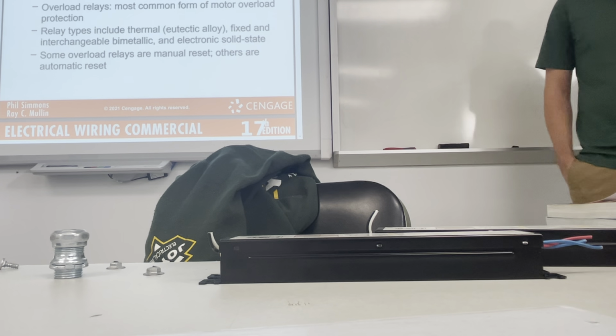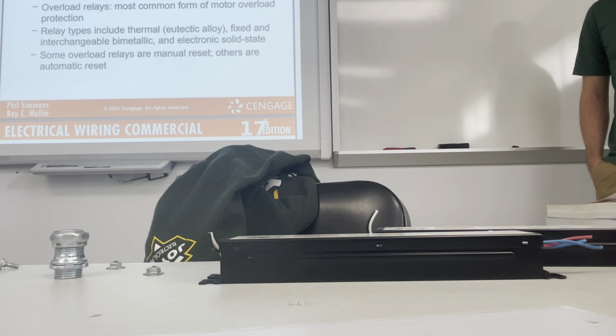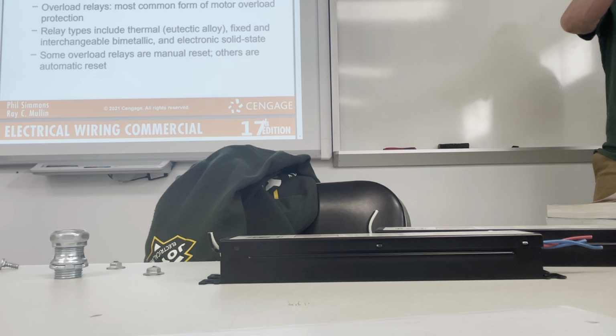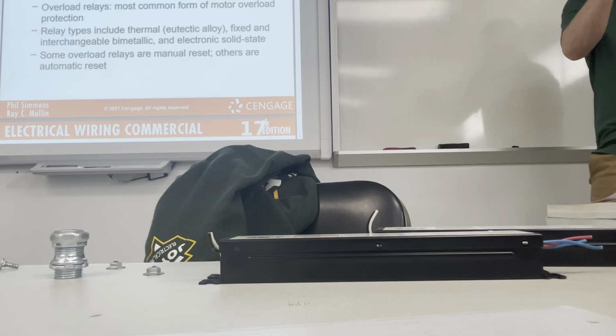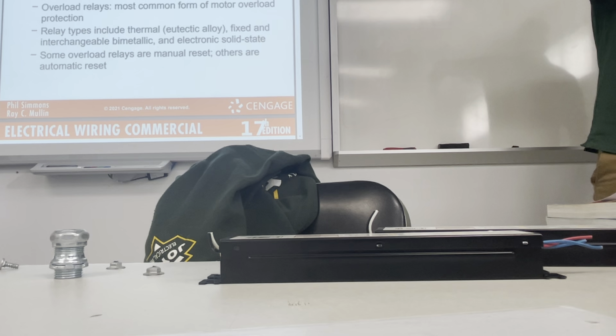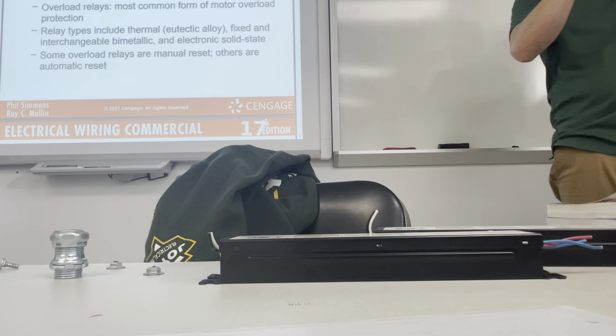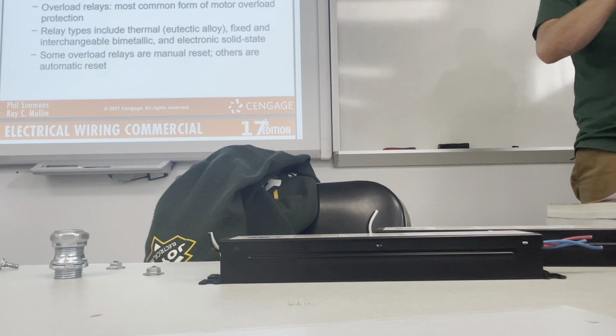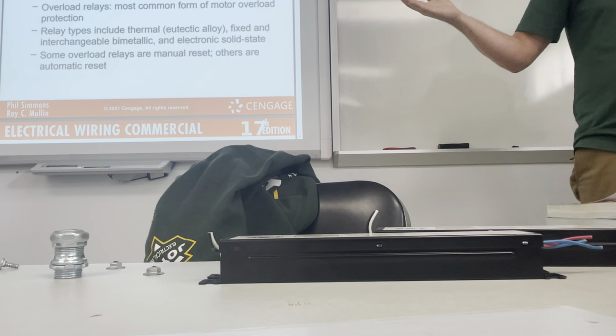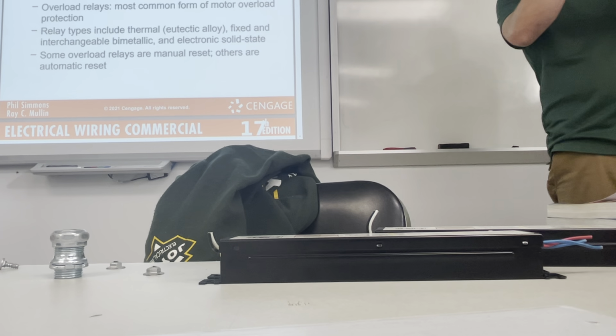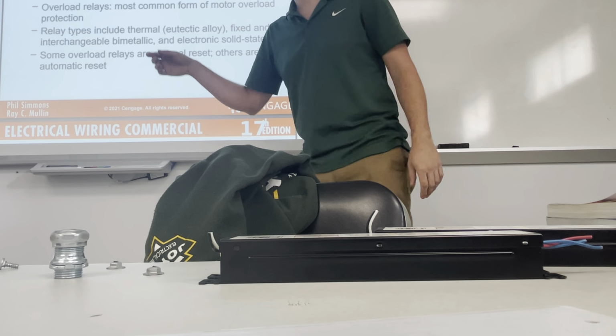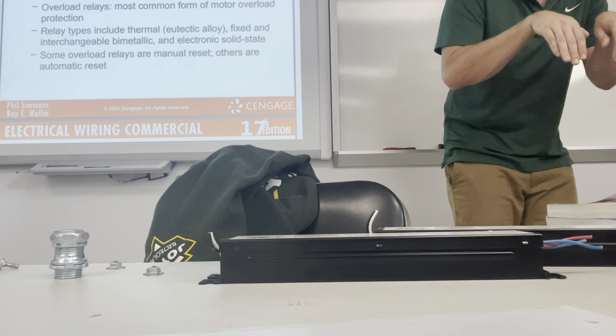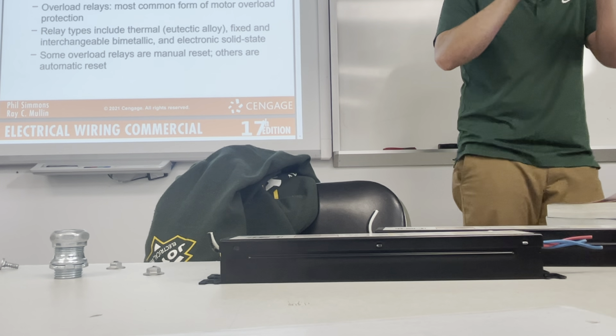Has anybody ever seen a thermostat hanging outside their house? Like not a thermostat, rather a thermometer, right? With that metal coil in there. That's a bimetal strip. And as it gets hotter, what happens to that strip? It expands. It turns your thermostat to a higher temperature. As it gets colder, it contracts, turns that back down to a lower position because it's two different pieces of metal joined. And they are dissimilar metals. So if two metals are different, they're going to heat up, expand, and contract at different temperatures. Am I right? So when it starts heating up, it's going to start bending. And at a certain point, a bimetal strip in an overload will bend and break contact. It'll break contact until it cools down, turning that motor back on.